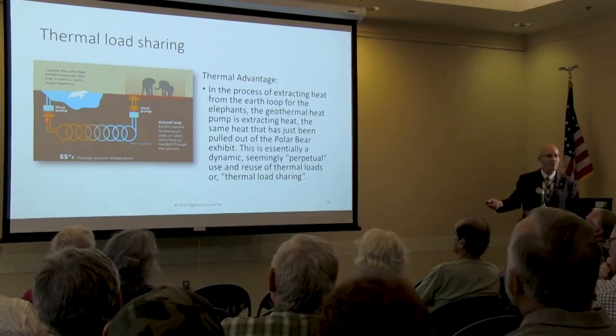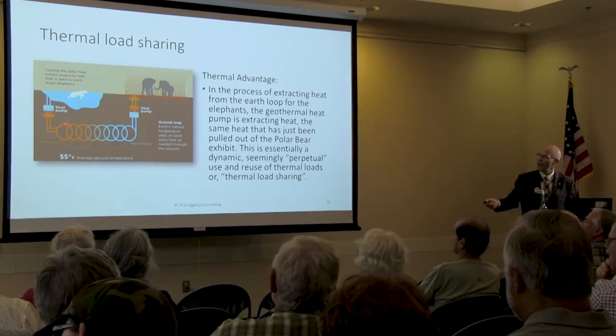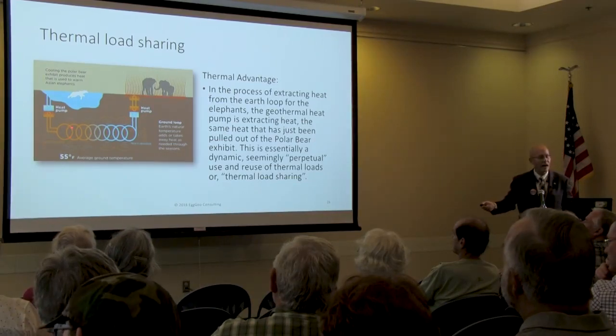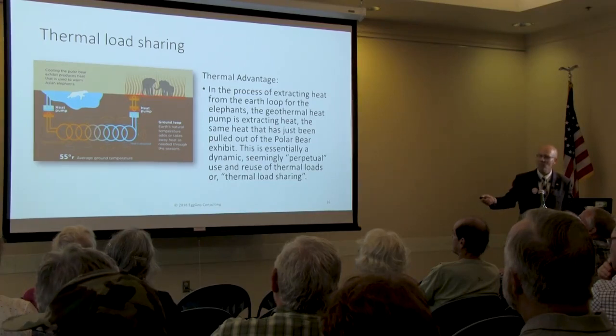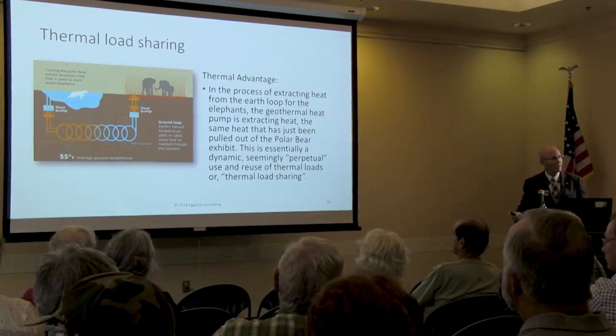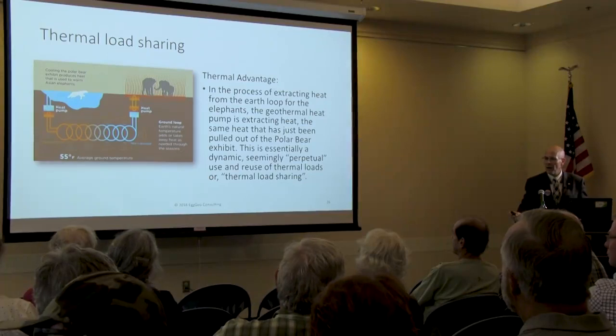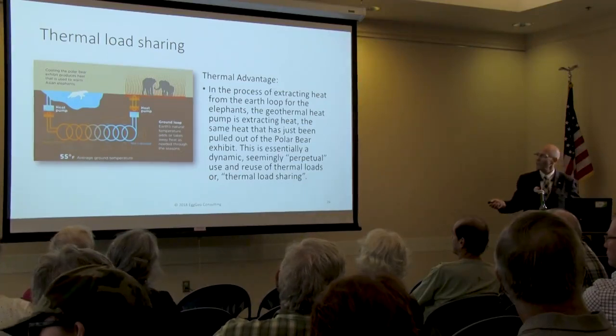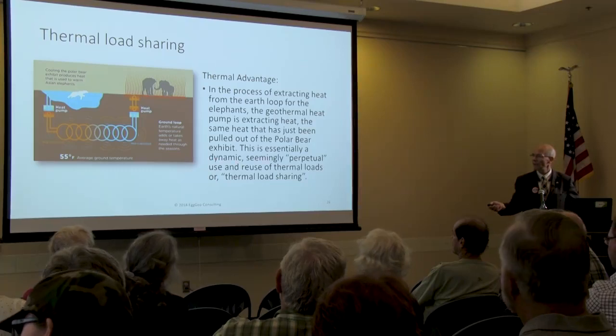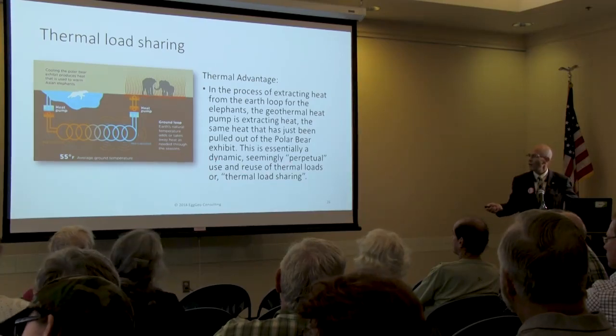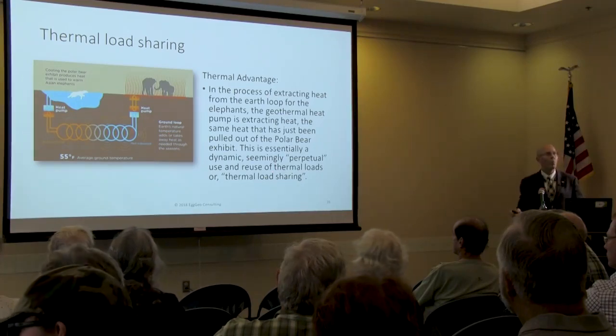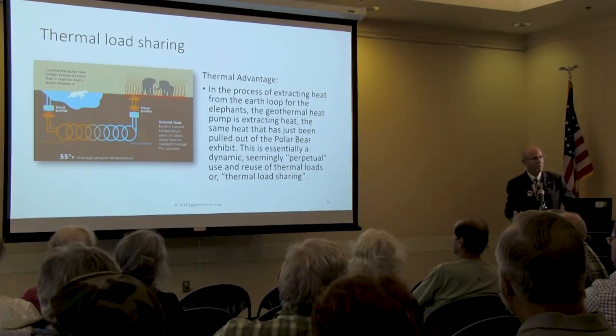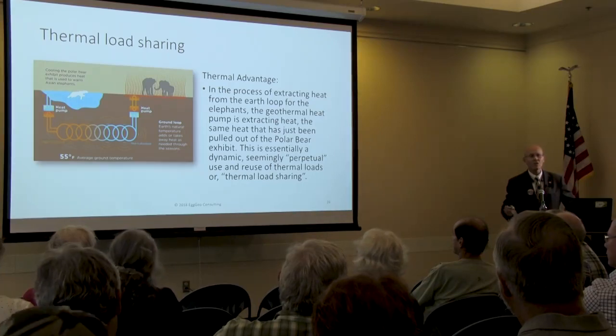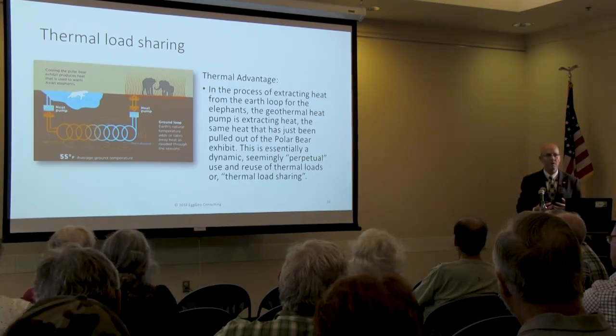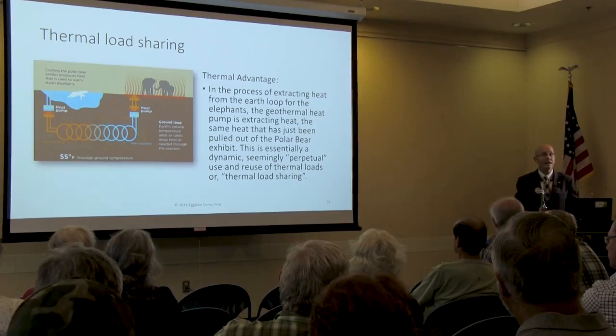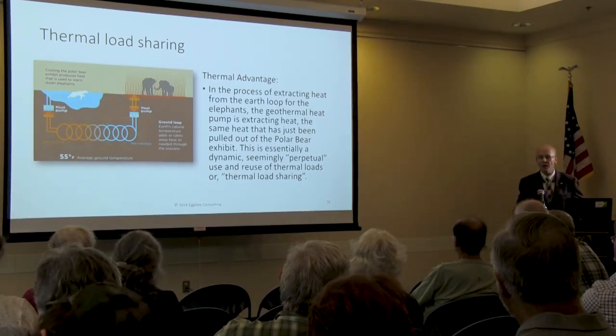Well, this common ground loop, which is kind of like a thermal energy grid, is having to pump BTUs out of the ground and out of the ground loop into the radiant in-floor system to keep it at 100 degrees to keep these African elephants comfortable. This is essentially a dynamic, seemingly perpetual use and reuse of thermal loads. You take what was a 5.0 COP heat pump, and because it's sharing energy with other heat pumps on the system, it can go up to 7, 8, 10, 11 COP when you're sharing energy like that.